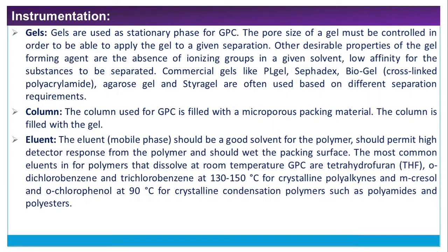Then the eluents are the mobile phases. As we know, they should be fresh. We have to make a constant supply of this eluent. It should be a good solvent for the polymer, should permit high detector response for the polymer, and should wet the packing surface. Whatever the packing surface of the column, it should be kept wet and should not get dry. So for that purpose we have to use this type of solvents.